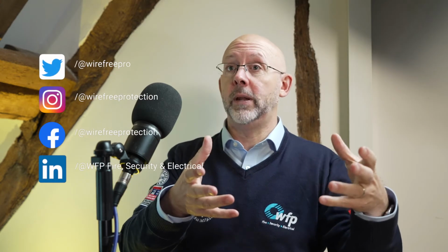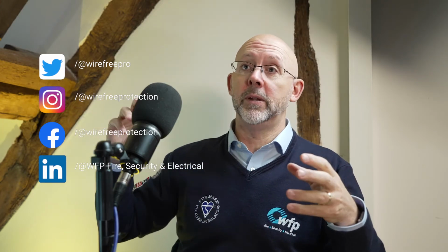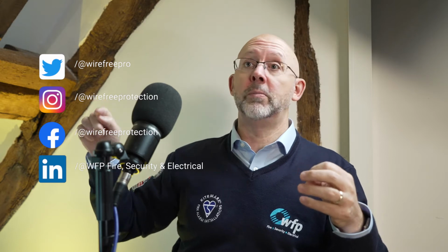So non-addressable is what fire alarms came from originally. So it's a box, a control panel. It's a wire that comes from that to the break glass, which is the red box by the wall. And then it goes from the break glass to a smoke detector, and then 2 or 3 small smoke detectors, and it might come down to a break glass. And if any of those things on that wire operate, the fire alarm panel flashes up an LED saying zone 1, and you know anything that's on that wire. So zone 1 is the left hand side of the building, for example.